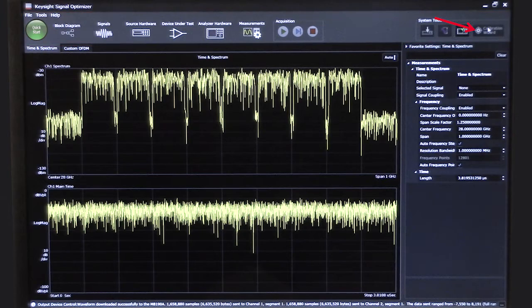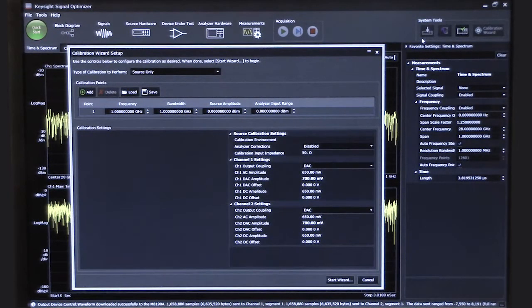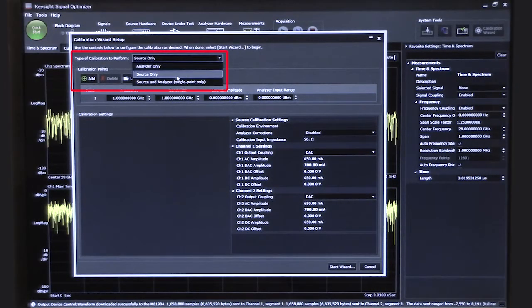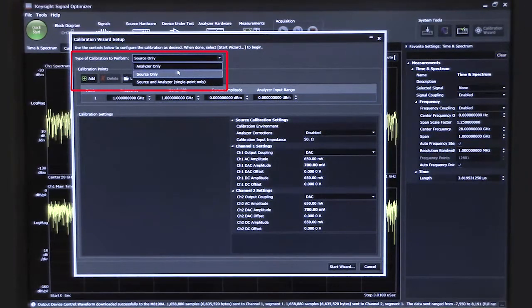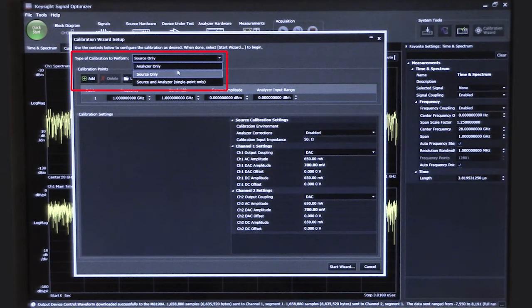So I'm going to click on the calibration wizard. We have three different types of calibrations we can choose from: we can choose to do a source-only calibration, we can do an analyzer-only calibration, or we can calibrate both the source and the analyzer. This includes anything between the device under test and the measurement equipment — so this could be cables, filters, amplifiers, etc.